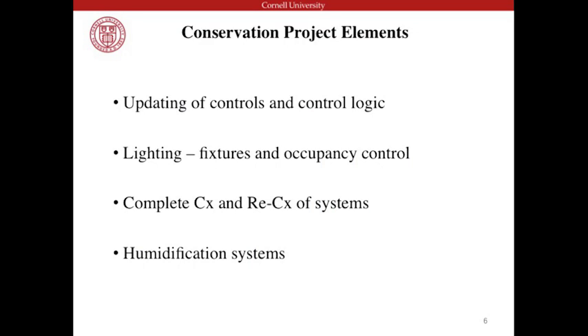We looked at updating building controls, really trying to optimize how we brought air into a facility, minimize reheat, minimize the amount of time that spaces were occupied when they shouldn't have been, minimize ventilation air coming in when we really didn't need extra ventilation air. We did a lot of recommissioning of systems. We found that our systems degraded over time. Recommissioning, we could bring those systems back to new, reducing the overall energy use.